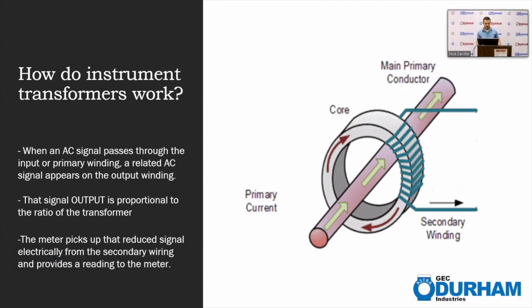Okay, good. Let's dive into a little bit of the theory of how instrument transformers work. So there's going to be an AC signal that passes through the primary conductor. And when that happens, there's a related AC signal that appears on the secondary or the output winding. Now that signal is going to be a ratio or a proportion to the primary amps that are going in. So the meter is going to pick up that reduced signal and transmit it through the meter.